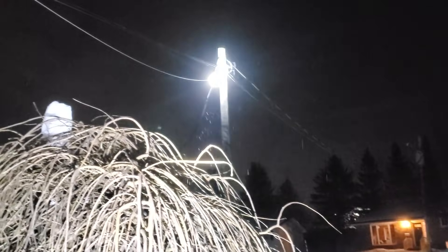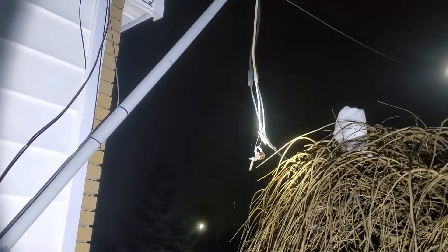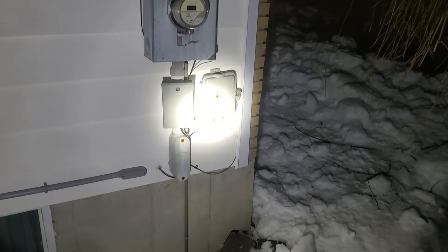There's the lag bolt that was in the house — it ripped right out. The way that's tweaked, there's a good chance it might have broken a lug inside the meter box. So before we do anything, we're going to go up to that pole and disconnect the two hots, then get that cut off the mast, coil it up while it's de-energized, and hang it up at the top of the pole. We'll contact the homeowner and get a permanent electrician to rebuild the mast — then we'll come back and hook the loop back up.